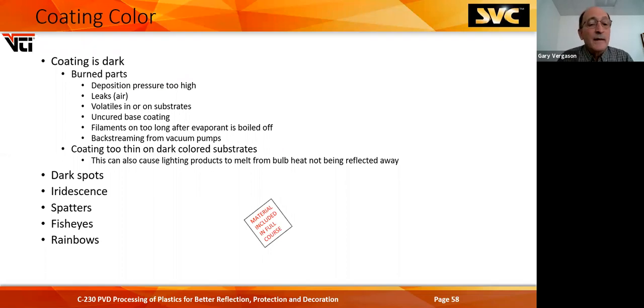Coating color. Your deposition pressure could be too high. You've got air leaks. You've got volatiles in or on the substrates. You can have uncured base coating. Your filaments are on too long after the evaporant's gone and you're burning your parts. You can have backstreaming from your vacuum pumps. Coating can be too thin.